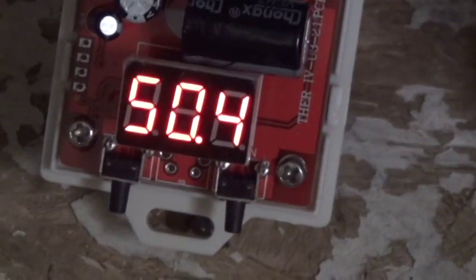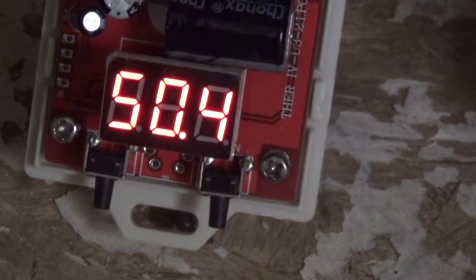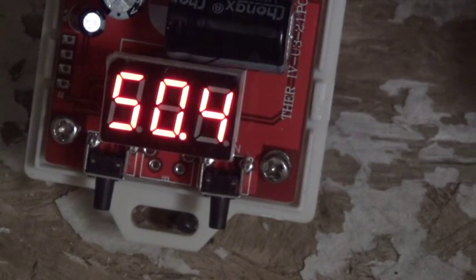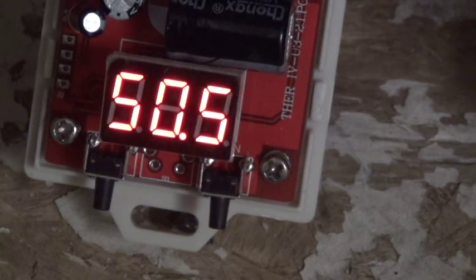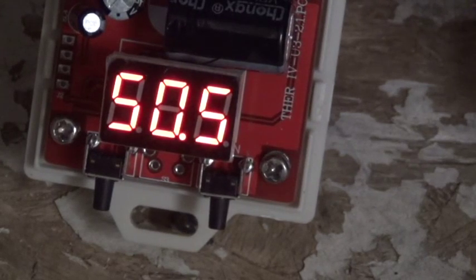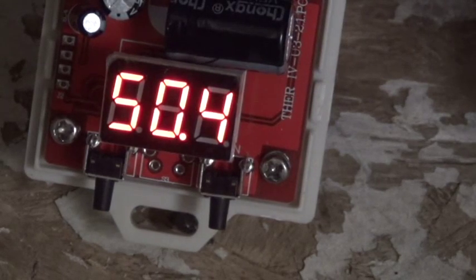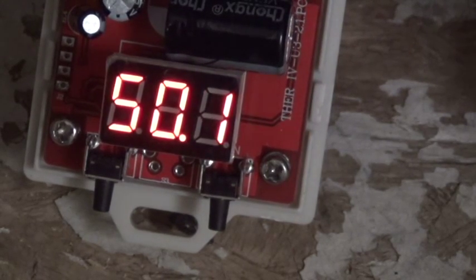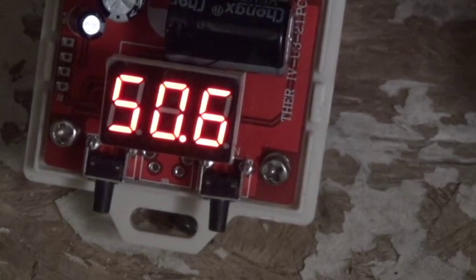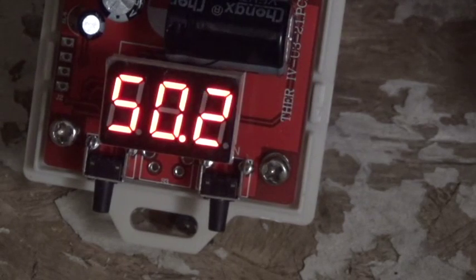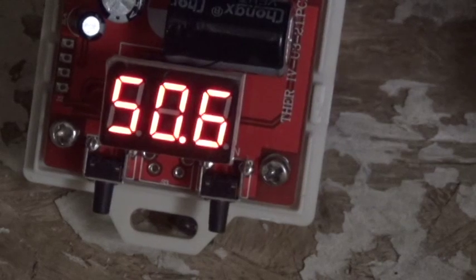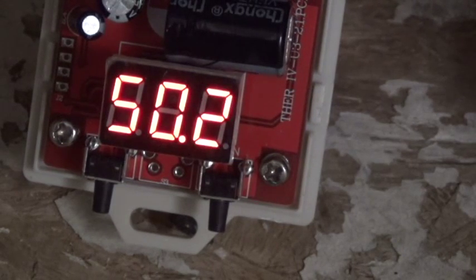I'm going to turn off the lights here so you can see the display a little better. Right now it's just cycling between 50.3 and 50.5 volts. Right now the battery is at 50.4. As the charge goes up it will turn the relay on, as the charge goes down we'll turn the relay off. I have this tight - there's not a lot of voltage in between 50.3 and 50.5, so this is going to be cycling quite quickly. This is just for demonstration purposes. In reality we'd set this up quite a bit differently.